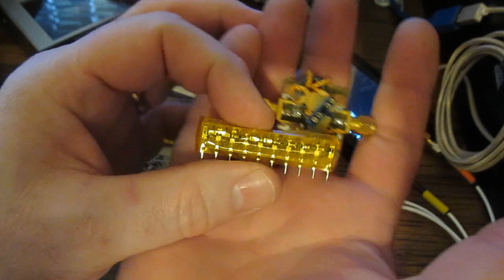Then I made up various standards. This is just a series of capacitors. These range from 1 picofarad up to 100 picofarads, and basically after I calibrate the instrument, I can attach these capacitors and basically do a sanity check. Normally you would just insert your crystal here.